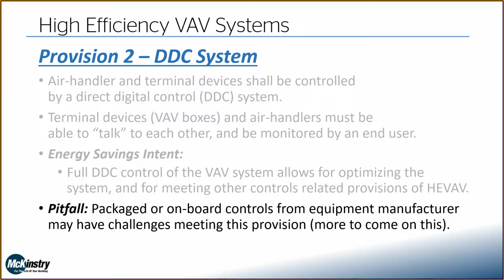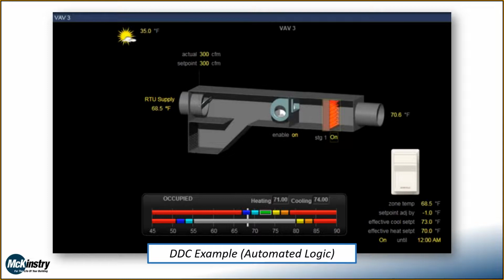The pitfall here is if you are looking to use packaged controls or onboard controls that come with the equipment provided by the manufacturer, you might have some challenges in meeting this provision, and there is definitely more to come on this on the control side. So here's an example of a DDC front-end, Automated Logic. This is looking at a VAV box. As an example of how this can assist with troubleshooting, you can see here the reheat is on, but we're only seeing a couple degree temperature difference across that coil. So this was an example of a failed VAV box, or failed reheat, rather.